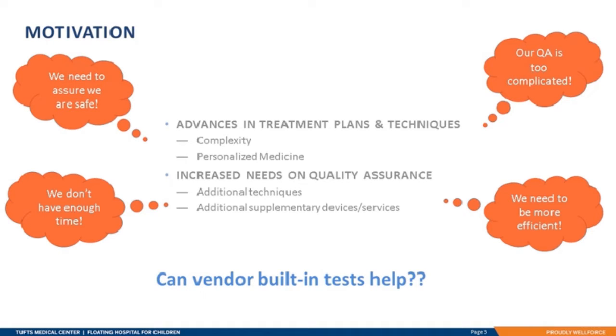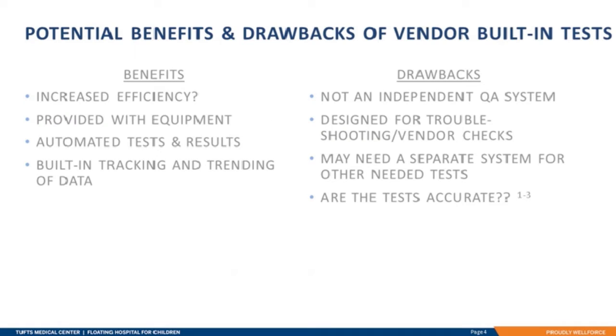The question of whether these built-in tests can be used to replace other daily QA is frequently asked. So when our clinic was looking at setting up our daily QA program on our new Linac, we wanted to assess how best to utilize these supplied tests. The biggest argument against using these vendor-supplied system tests as a replacement is that they are generally not designed for routine QA. They are not an independent QA system, but instead are designed as troubleshooting tools for physicists and service engineers for the vendor. This often means that the tolerances for machine performance from the vendor point of view may be different than recommended tolerances or the tolerances that the clinic may want to assess. Therefore, these provided tests are not a replacement of an independent QA platform.